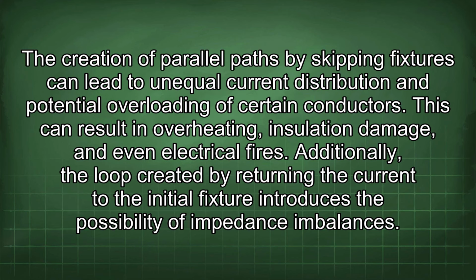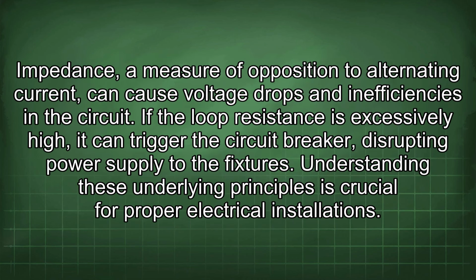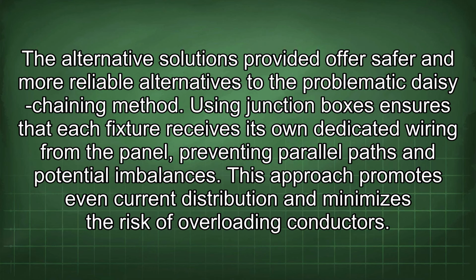Additionally, the loop created by returning the current to the initial fixture introduces the possibility of impedance imbalances. Impedance, a measure of opposition to alternating current, can cause voltage drops and inefficiencies in the circuit. If the loop resistance is excessively high, it can trigger the circuit breaker, disrupting power supply to the fixtures. Understanding these underlying principles is crucial for proper electrical installations. The alternative solutions provided offer safer and more reliable alternatives to the problematic daisy chaining method.